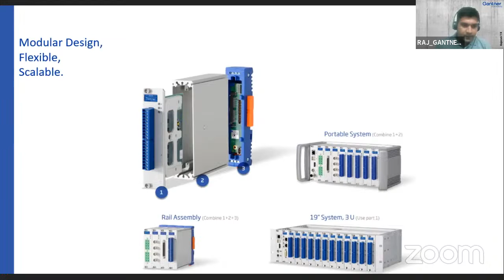Another point to stress: we believe customers should be able to connect any kind of sensor directly to our IO modules. We have more than 30 to 40 kinds of IO modules, both dedicated and universal, so you don't need external amplification or signal conditioning to connect sensors to the DAQ system. Whether it's voltage, current, thermocouple, IEPE, cryogenic, or different types of strain gauges, you can connect directly to our IO modules, which have 24-bit ADCs built in to handle sensor connectivity.